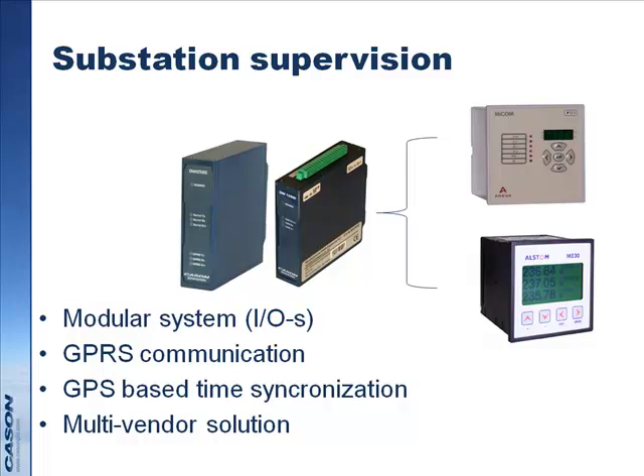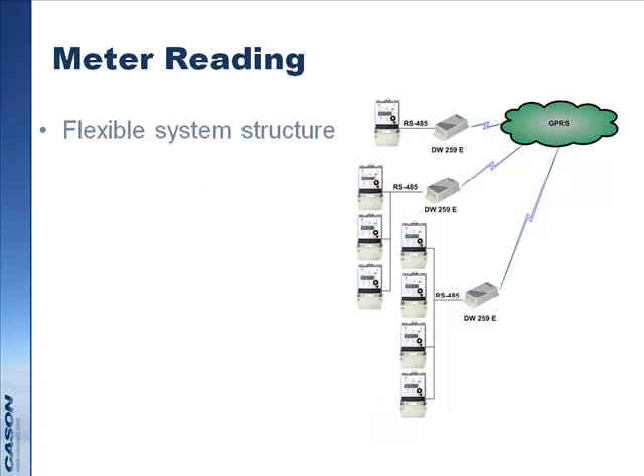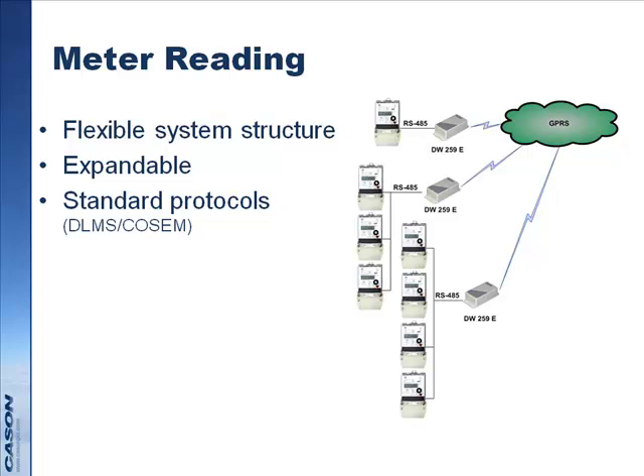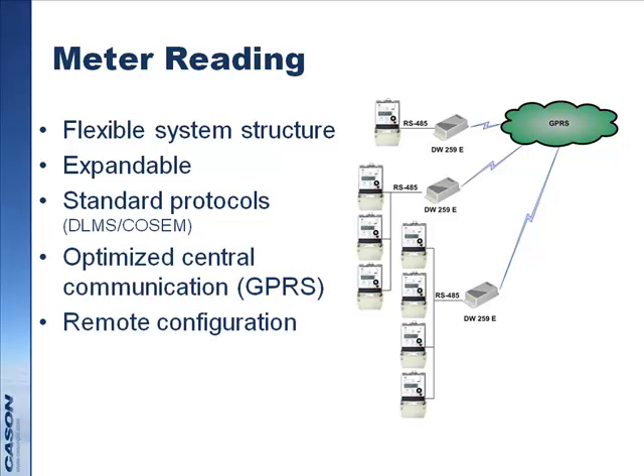So again, we are not delivering the substations themselves, we only do the monitoring, telemetry, controls, and measurements on those. Also meter reading for large customers, or in fact for substations as well. This is basically establishing the amount of energy which we feed into the feeder lines, for example 11 kV loops, to be able to create a last mile balance.